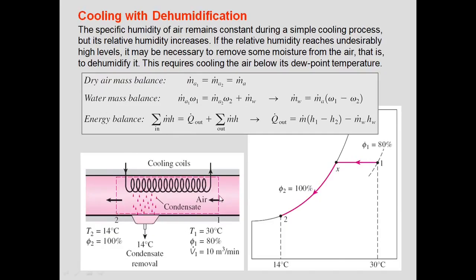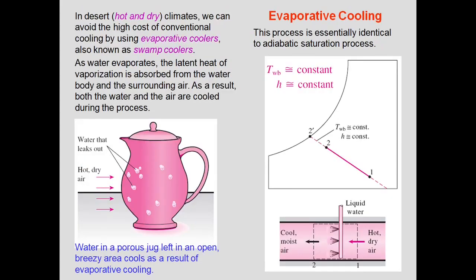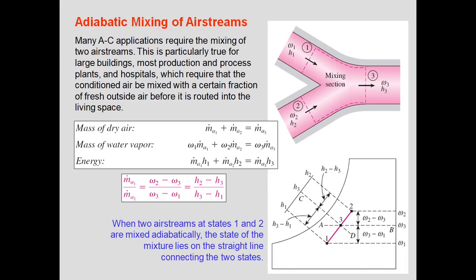In cooling and dehumidification, air is first cooled until it reaches dew point temperature, after which condensate forms and moisture content drops. This is shown on the chart from point 1 to point X on the saturation curve. Evaporative cooling involves spraying liquid water that evaporates directly into the moist air stream.